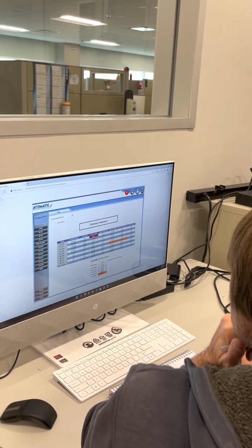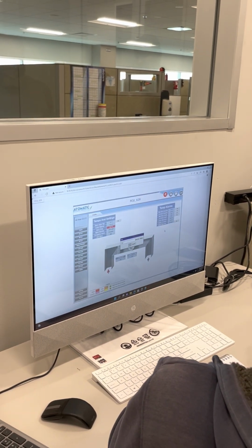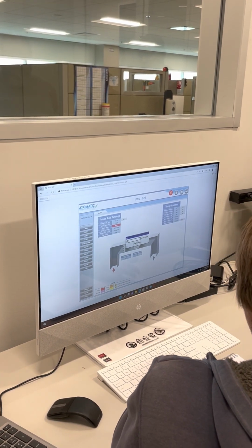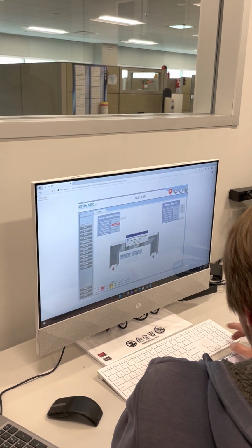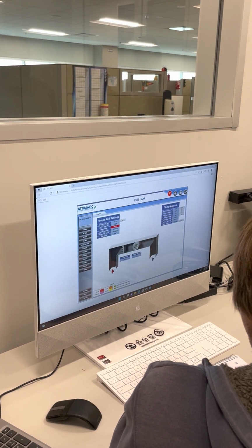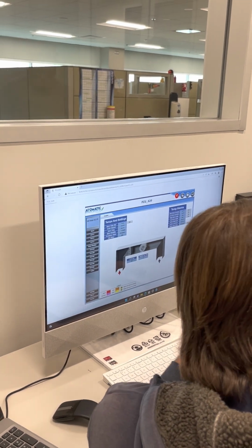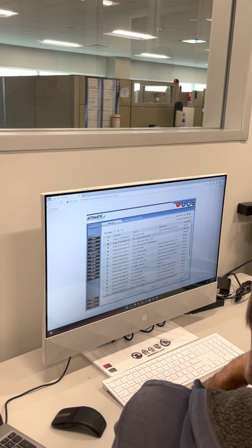So if we go back and put this back to 30 minutes, put this back to 5. Boom, you see how now it cleared out, right? You see it cleared out itself because we fixed the temperature, basically is what we did in there. And then if we go back to alarm, since we acknowledged it, let's see what happens. Yep, there you go. So it came back.